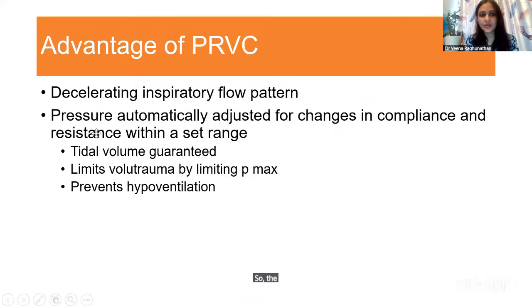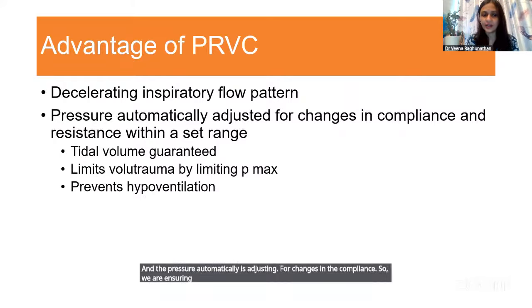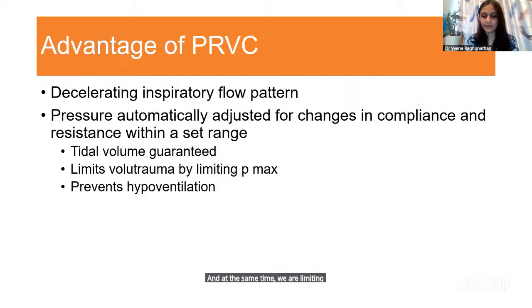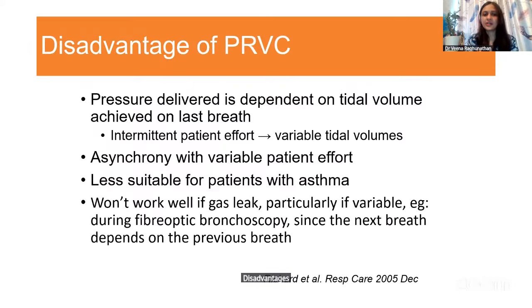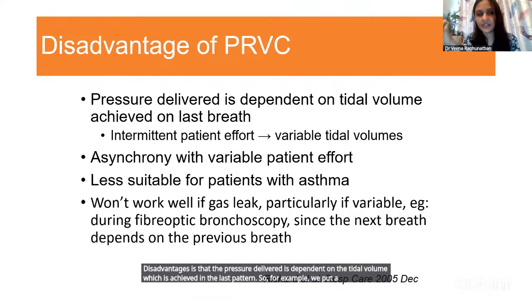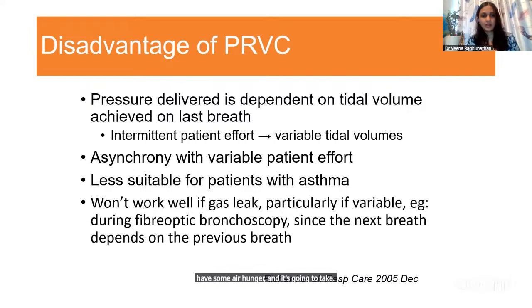So the advantage is it is using the decelerating flow pattern and the pressure automatically is adjusting for changes in the compliance. So we are ensuring the tidal volume delivery and at the same time we are limiting the pressures. Disadvantages: the pressure delivered is dependent on the tidal volume which is achieved in the last breath. For example, we put a patient on PRVC and the patient is starting to have some air hunger and is going to take more breaths. So actually the ventilator will feel that the compliance has improved and it may end up giving lesser pressure in the next breath, which will cause more problems to the patient. So there can be some asynchrony with variable pressure.